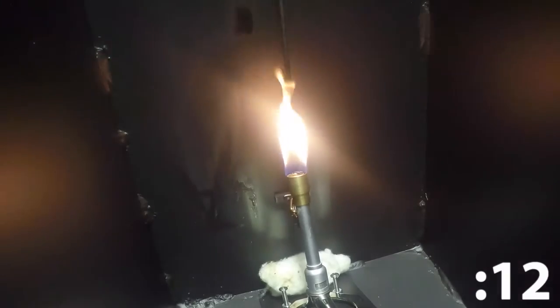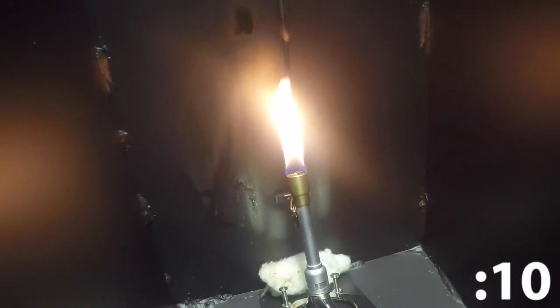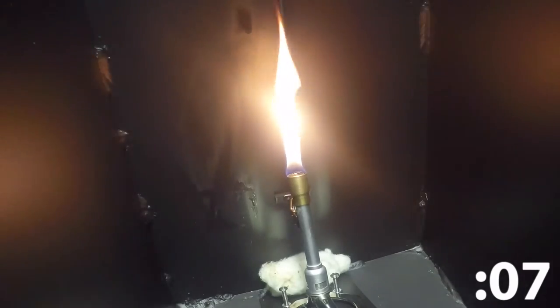The second sample's jacket is charred and hardened around the core after the flame application. This is the desired effect from a flame-retardant cable jacket.